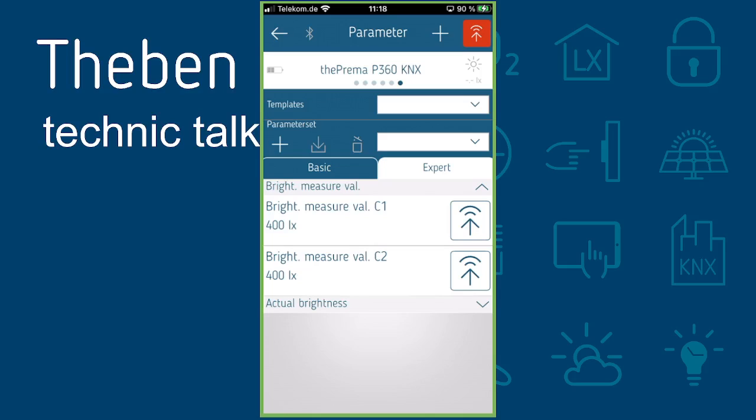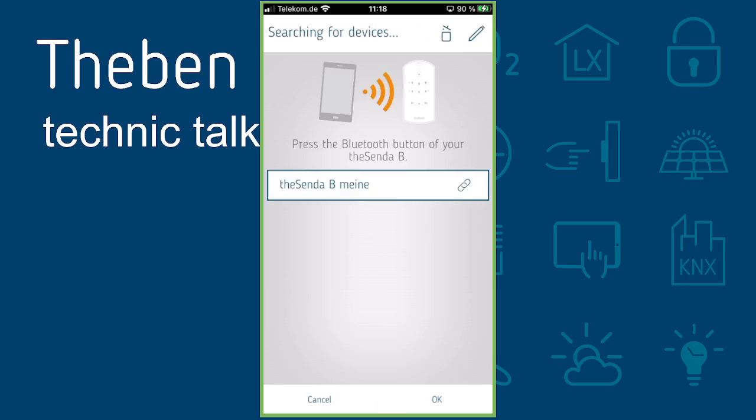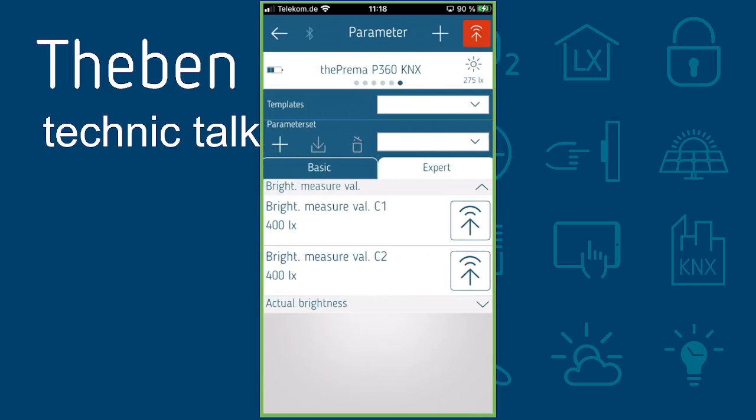Currently there is no communication with the theSenda B, so we need to link it by clicking on this icon — 'My theSenda B'. Once linked, you can see the flashing icon in the top left, and immediately on the top right the live lux reading appears — for example 209 lux. If I cover the sensor with my hand, the value changes immediately, confirming it is a live lux meter showing the real value measured underneath the sensor.